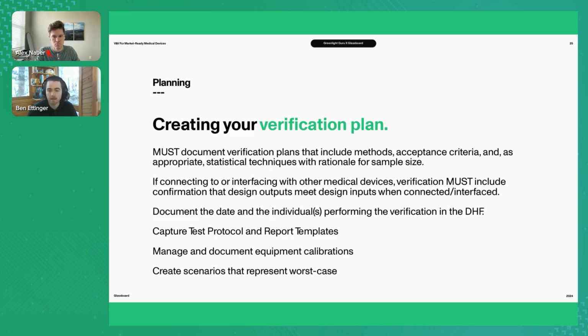The final one here is a big one. Create scenarios in your test plans that represent worst case. If the FDA doesn't feel like you represented worst case sufficiently, they will come back and ask you to revisit the testing and revamp it for worst case scenarios. So this is where I like to say, dream the nightmares, because if you get your product into the hands of enough people, they will find a way to use it in ways that you had never hoped or never thought people would. So really do your due diligence here on the front end, thinking about all the worst case scenarios for how the product could be used and test to it.